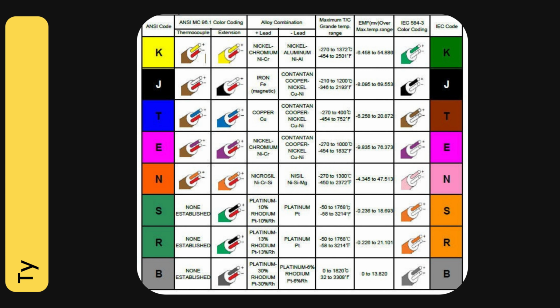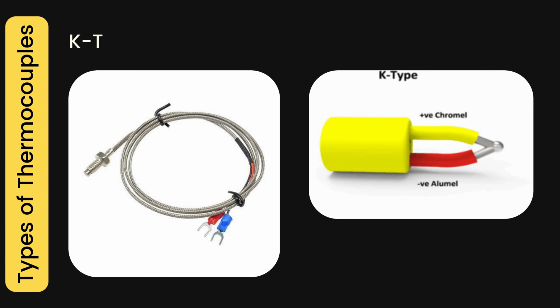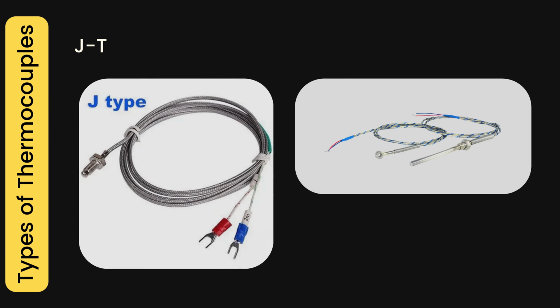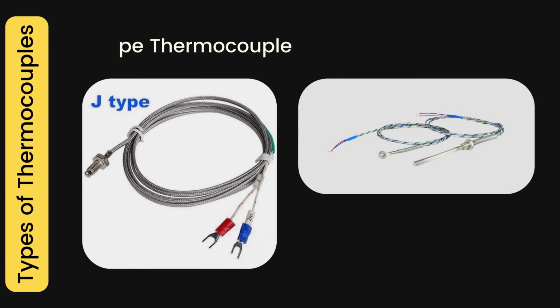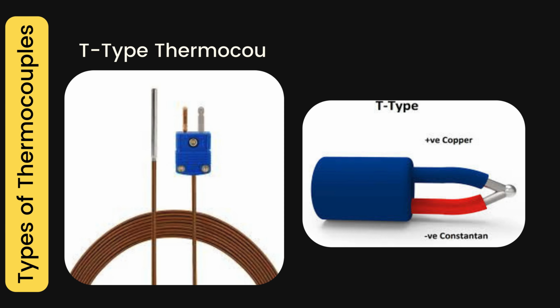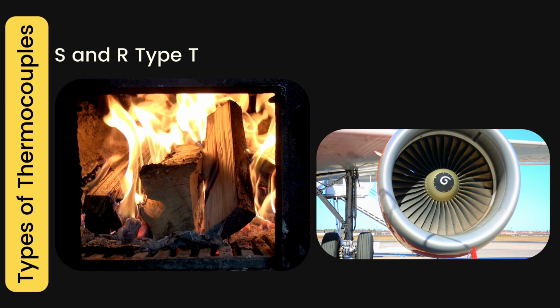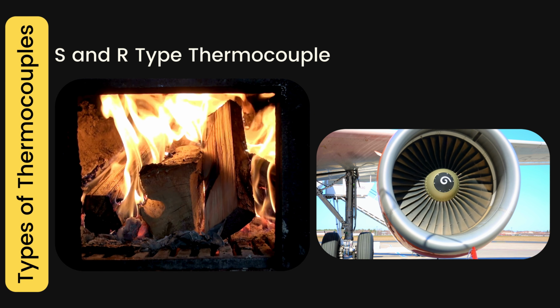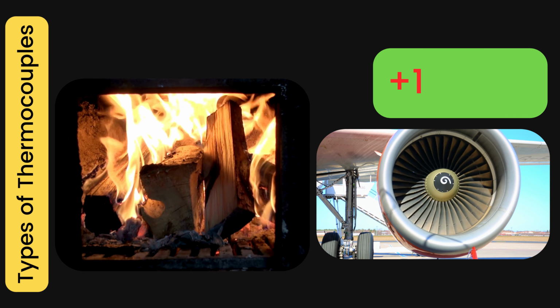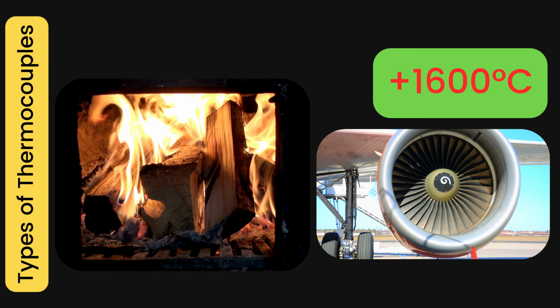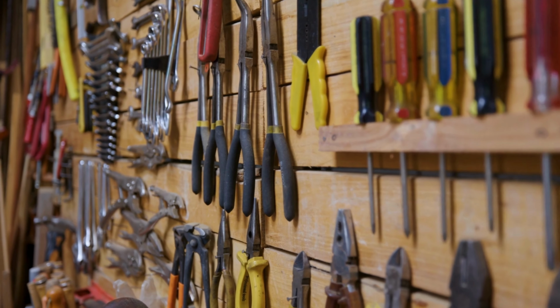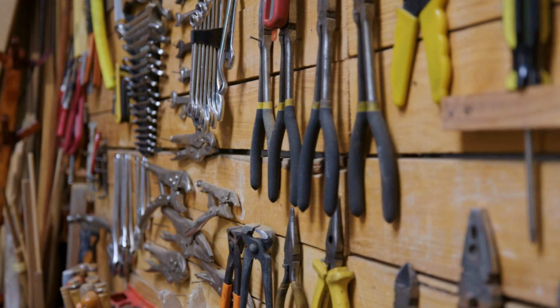Not all thermocouples are the same. Engineers use different types depending on the environment. For example, Type K, made from nickel chromium and nickel aluminium, is very popular for general use. Type J is good for lower temperature ranges. Type T works well in very cold conditions. And for extreme situations, like furnaces or turbines, we have Type R or S, made from platinum, which can withstand temperatures above 1600 degrees Celsius. Choosing the right type is like choosing the right tool from a toolbox.